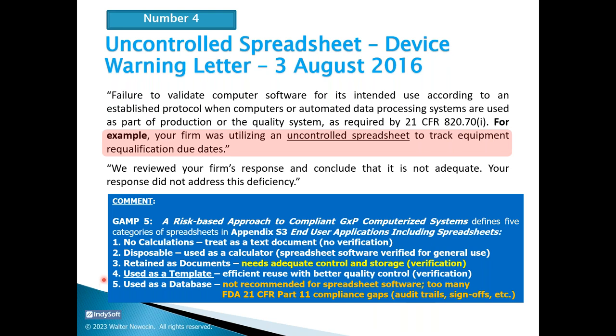So how should we use a spreadsheet? For my team, we're dealing with calibrations where we use test points and take raw data, then try to determine if it's in or out of specification, and come to some sort of conclusions, documentation, and actions. We ultimately went from using individual spreadsheets, which got us in a little bit of difficulty because they weren't very well controlled, and had different variations of them, which got us into a bit of a situation. We came out of that learning by coming up with a different way to handle calculation of raw data for calibrations, where we came up with a template, a spreadsheet template for each that matched every calibration procedure we have.